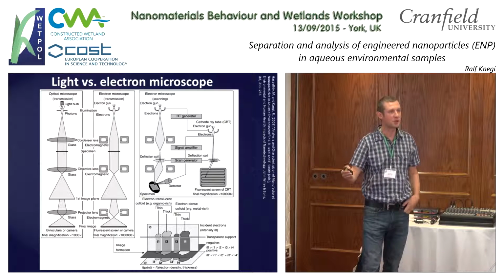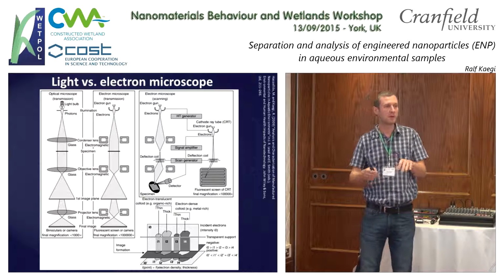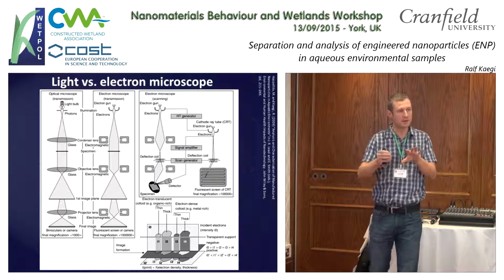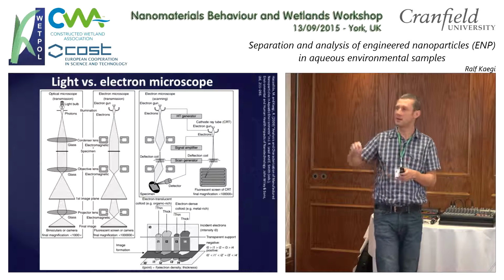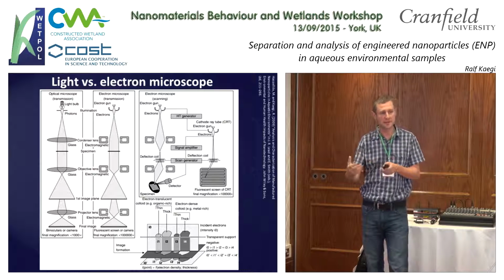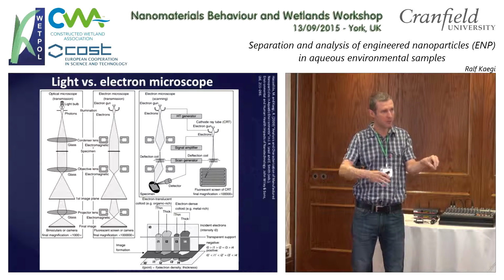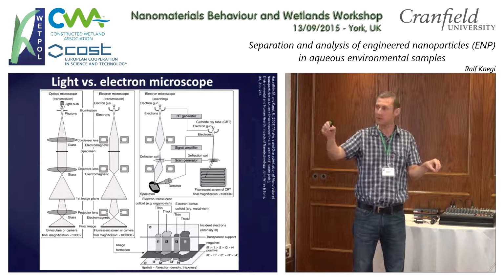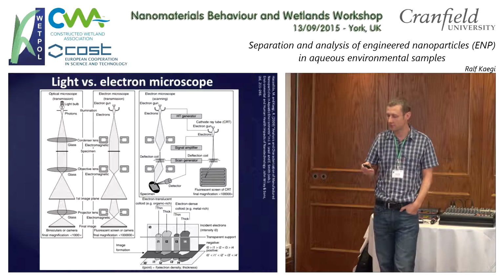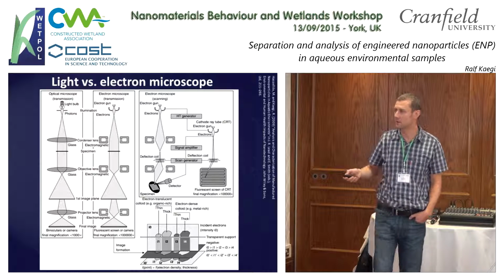That's fundamentally different in a scanning version. In a scanning version, you focus the electron beam on a point of your sample. There you have a lot of interactions, creating a lot of signals. You detect the signals, and a pixel of your screen is then modulated according to the intensity of the signal that you detect. That means you scan your sample, you scan on your TV screen, and you modulate the intensity on your TV screen according to the signal intensity detected by this detector here.